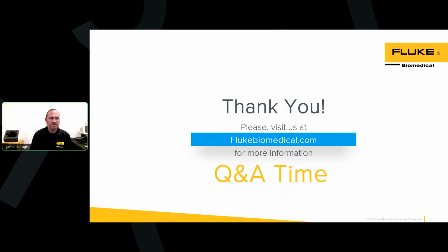The power to the machine would have to be on - the ESA would have to be on to run those tests. I don't think you could do it off. Though if you're talking about a medical device, you could test it on and off, depending on what your standard requires. Do you do all your electrical safety testing with power on, and then all of it again with power off? With NFPA 99 standards you're not required to go into that depth, but a lot of manufacturers run hybrids of 60601 and 62353, kind of running hybrid electrical safety standards. So you may have to test with both power on and off, but the instrument itself does have to be on.